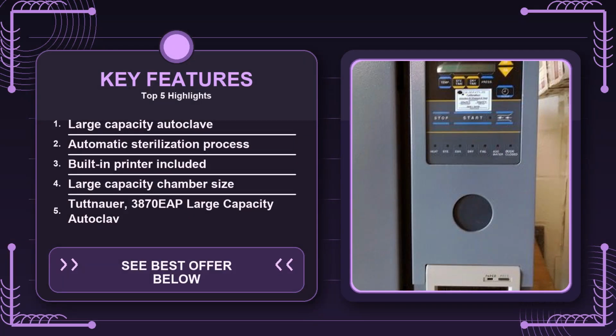necessity. What about reliability? Tuttnauer is a name you'll see on many sterilization units, and their service network is fairly robust in most regions. The 3870EAP uses a standard pressure sensor and temperature probe that are designed for easy replacement, which means you don't have to send the whole unit back if something fails.